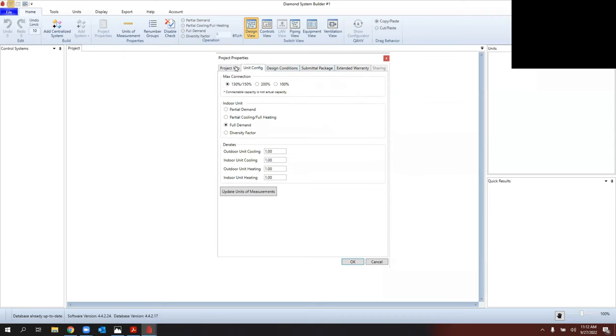Mitsubishi tracks these on the back end — if a lot of projects come in as Plan and Spec it helps develop inventory needs, but that's at least a year to a year and a half out. So 99% of the time, select Design Build. Walking across the tabs: always keep the 130% max connection for residential. The only time you might change this is on a ducted multi-zone system — many DSGs recommend not connecting over 100% capacity to ensure enough latent capacity for that coil.